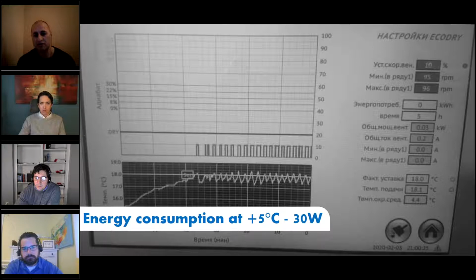Another data center in Moscow, Data Pro. There was a realized data center with an LHP system. Here you see the back of the rack where there is a dry connection for the LHP and no liquid in the servers, only in the back of the rack. And also there is redundancy, 1 inlet, 2 inlets and 2 outlets. And the tests show that servers without fans with LHP reduced energy consumption by 15%.